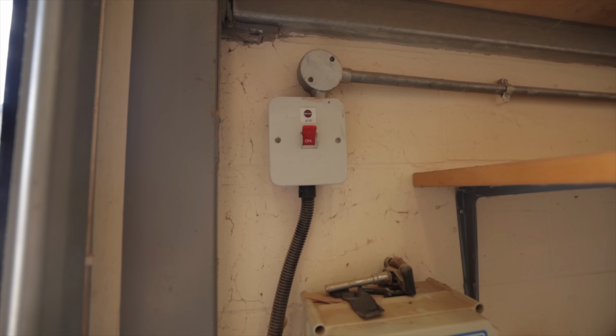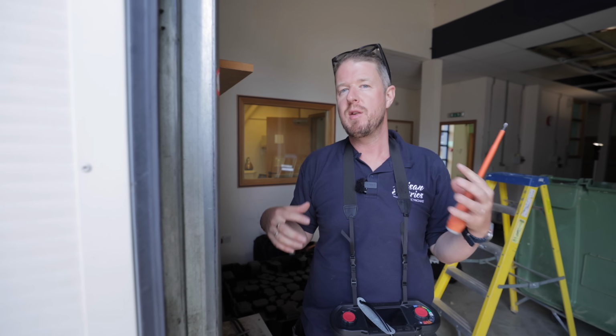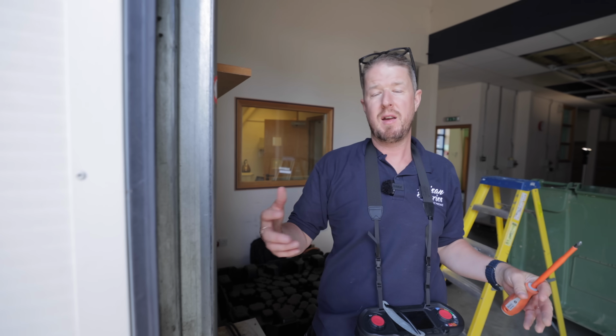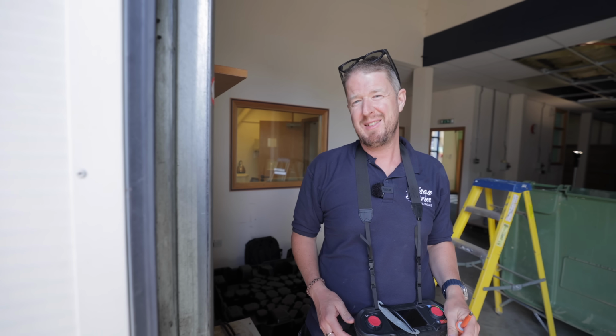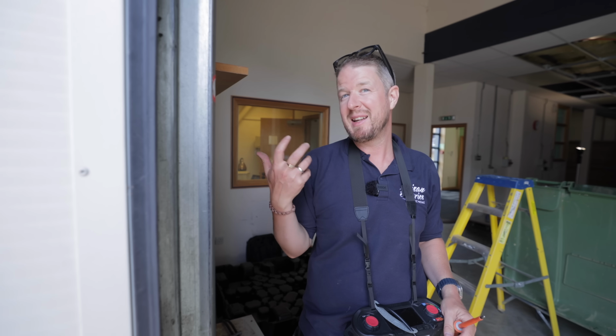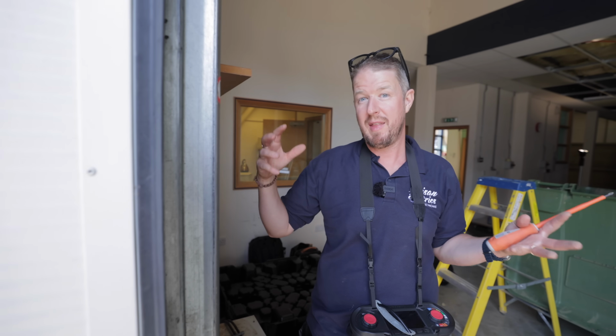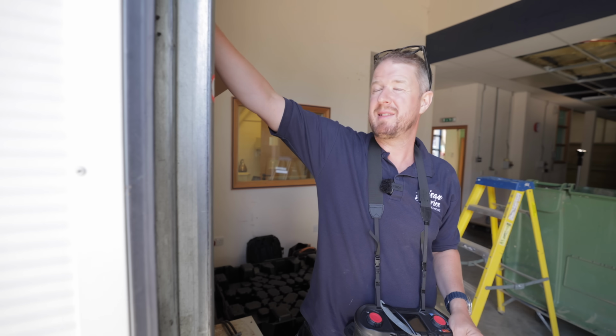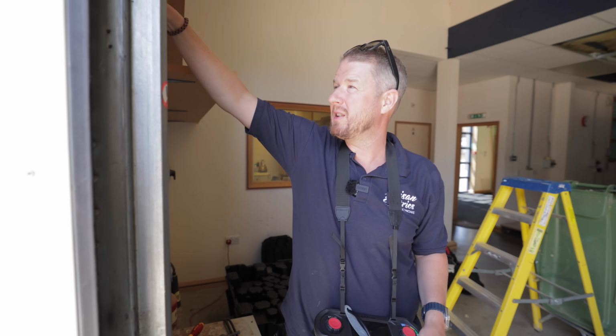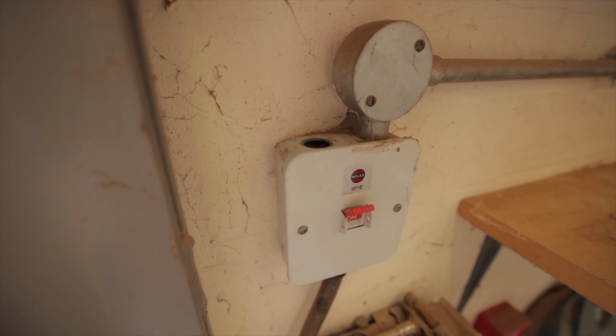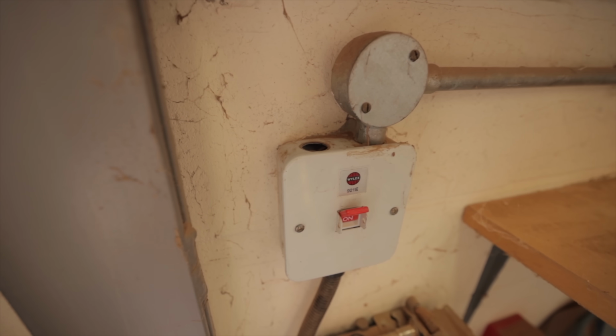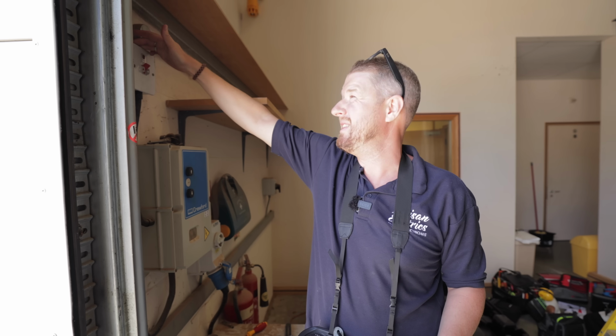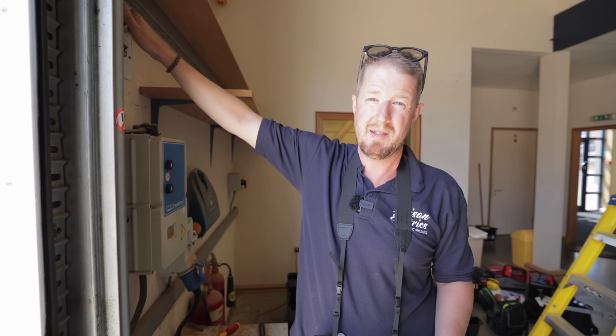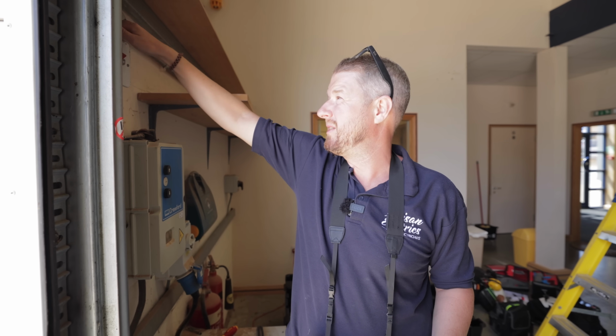Now, while we're going around and testing, it's important not just to test, but actually to visually inspect as well. And when you're doing an inspection, you're really using all your different senses, your touch, your sight, your smell, not necessarily your taste, but sometimes you smell a burning smell or a fishy smell or something like that, and you know that there's potentially issues. Here I've used my sense of touch. I've just touched the top of the isolator switch, and there's actually a big hole in there. So that is non-compliant, and that would be a C2 on the EICR. It's really easy to fix by just putting what we call a blind or blank grommet in there, just to fix that hole.